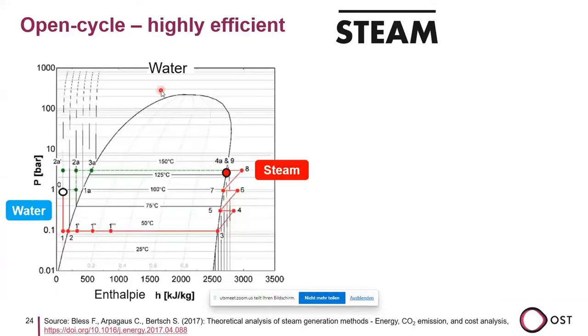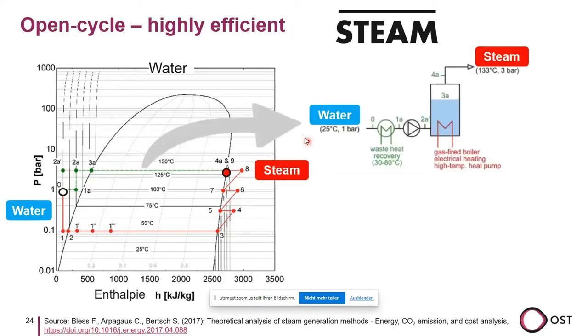So what is an efficient cycle for a heat pump to produce steam? We can illustrate that in the pressure enthalpy diagram of water. At the beginning we have water at one atmosphere or one bar, and we want to reach the steam here on the right. One way is to increase the pressure and then evaporate. In this system we have maybe a preheating, then a pump, a vessel, which is a gas-fired boiler or electrical heating, or even a heat pump to produce the steam.